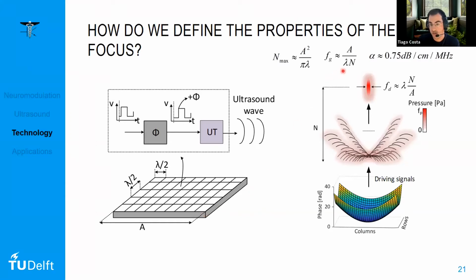And if we increase frequency to decrease lambda, you see here that each channel needs to be spaced by lambda over 2. This is to avoid grating lobes, which are side effects. You can see it as unwanted focal spots appearing in different locations in space. And to avoid these grating lobes, we have to space each element by lambda over 2. So if we increase frequency, the spacing decreases, and it becomes very challenging to design the electronics and to fabricate ultrasound transducers in such small spaces. So these are basically the trade-offs between the design of the devices and the performance.